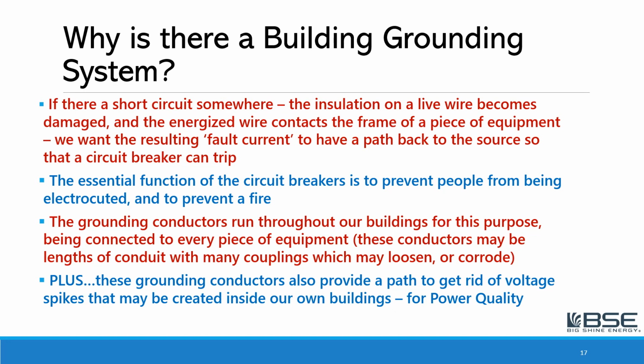If there's a short circuit somewhere where the insulation on a live wire becomes damaged, and that energized wire, the metal conductor inside the wire, contacts the frame or piece of equipment, we want the resulting fault current, as we call it, to have a path back to the source, meaning back to the distribution panel, so that the circuit breaker can trip. That's why we have circuit breakers. They trip and open the circuit when there's a sudden rush of current, meaning there was a short circuit or a fault of some kind. And that prevents people from being shocked, electrocuted, and also prevents arcing, which would start a fire.